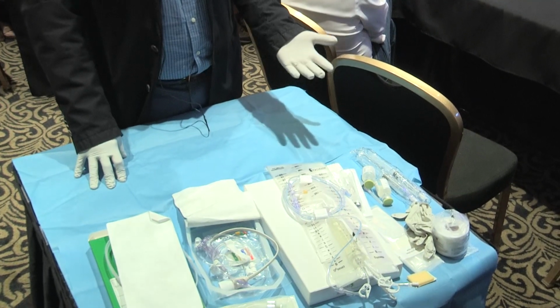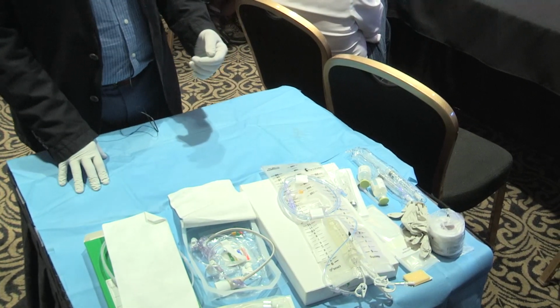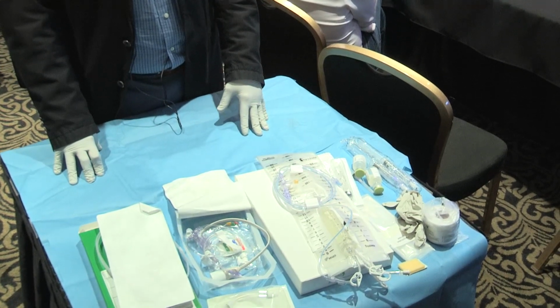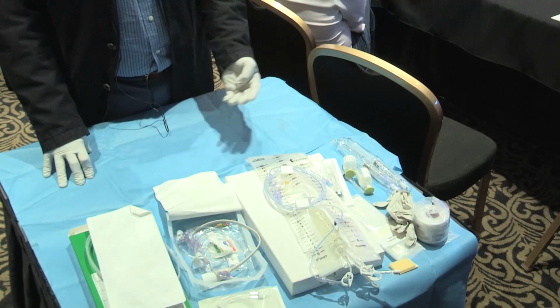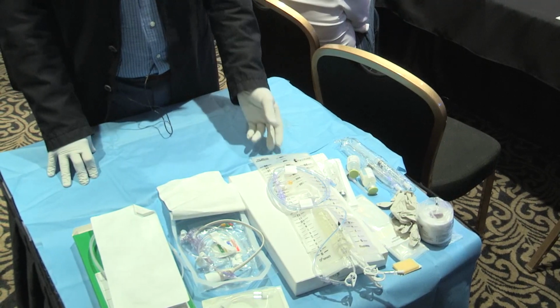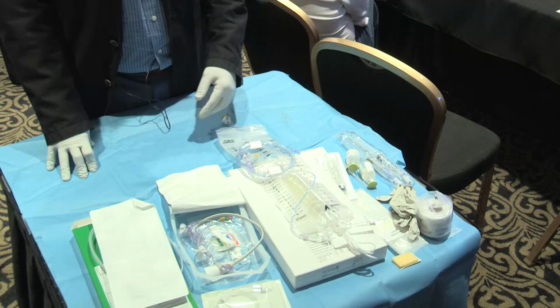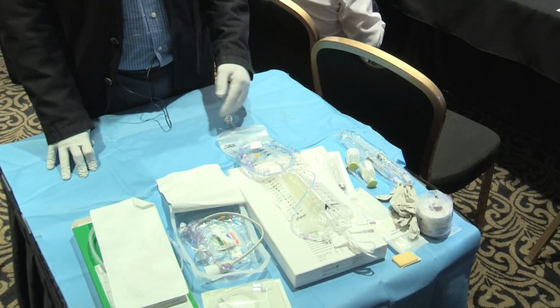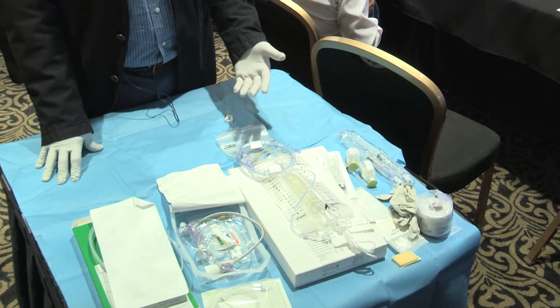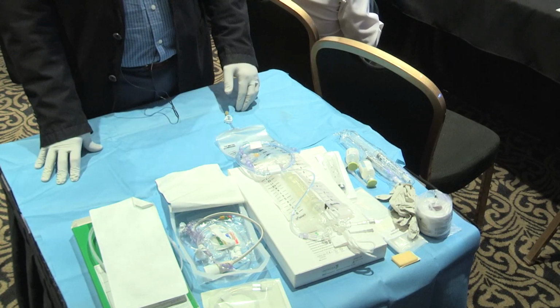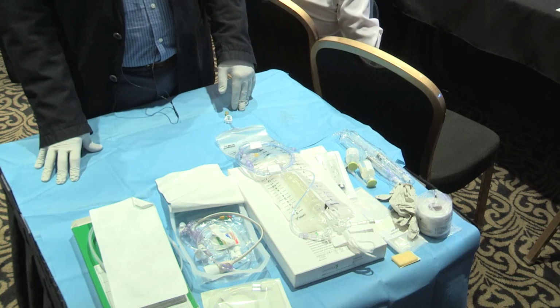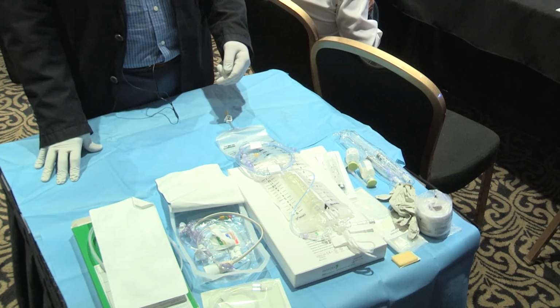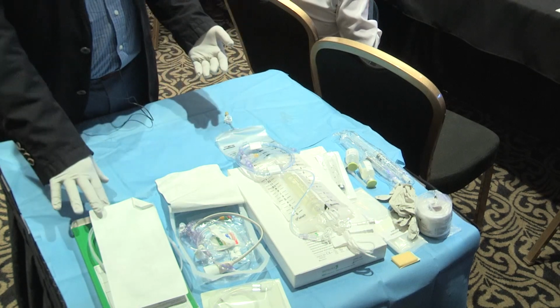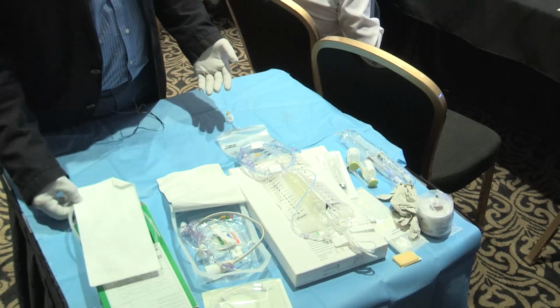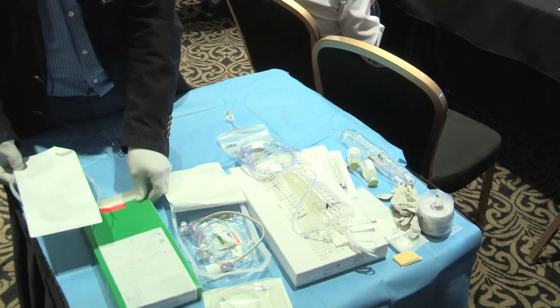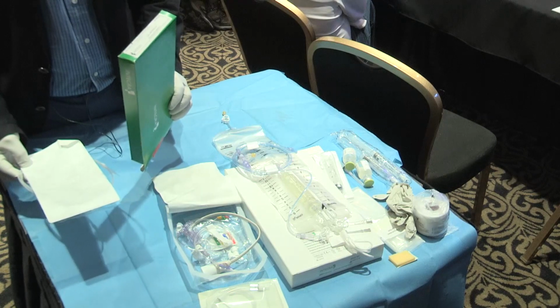So there are three things that need to be set up in order to be able to put this catheter. One is first the transducer. Second is the bag with the little chamber and the bigger bag where the CSF is going to drain, and these two need to be connected. These are normally done by the anesthesia techs. We have the luxury in our hospital to have them do that, but I'm not sure in every hospital that this is happening. And then finally, you have to set up the spinal drain, which is done only by us and has to be done totally sterilely.